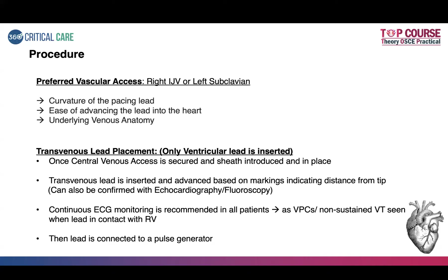So coming to the pacemaker programming. The usual mode that is kept is VOO mode. The ventricle alone will be paced at a certain level, whereas it will not have any sensing or any kind of response. There will be only a continuous impulse that is being generated, and that will lead to the cardiac action potential being excited, leading to contraction of the cardiac muscles.